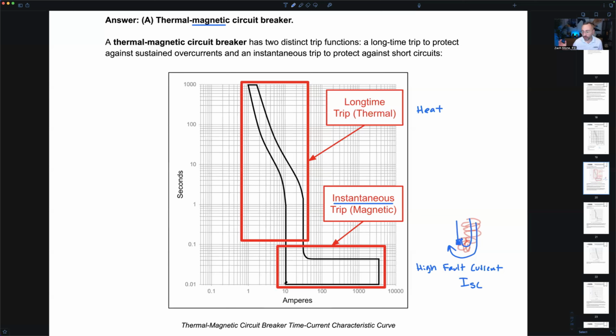All right, what about the thermal trip function, or the thermal region on the TCC curve? What is this designed to protect? Not high fault current, not short circuit current. That's our instantaneous magnetic region. Overload, said Mitch. Yeah, overload. Instantaneous trips as soon as possible. Overload, you've got a little bit of what built into it? You've got a little bit of time delay, don't you?